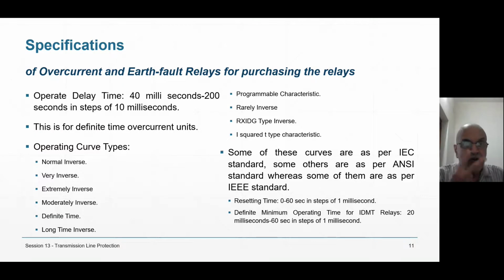Not only that, between two relays, you are keeping 0.25 second time interval. That is the discrimination time margin. That can be reduced to 0.04 second. Many advantages are there. Probably in the next, 14th class, we are going to talk about the different advantages of overcurrent relays, I mean numerical overcurrent and earth fault relays.